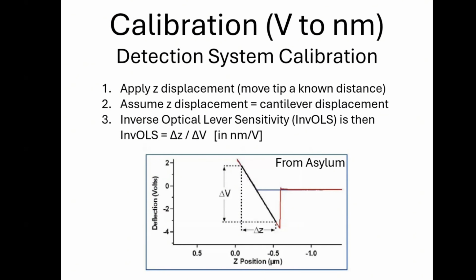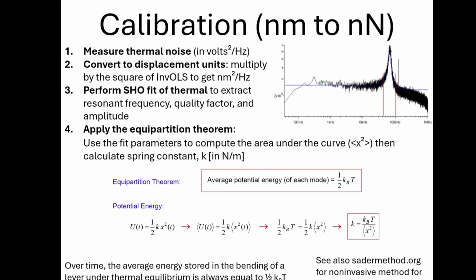First, we need to relate the photodiode voltage, the cantilever deflection in volts, to a cantilever deflection in nanometers. To do this, we do a force curve on a hard surface, where we move the tip a known distance and measure the deflection in volts. This volts to distance comparison gives us what is known as the inverse optical lever sensitivity, or invols, typically in nanometers per volt. Now that we have the deflection in nanometers, we recall that we determined force from Hooke's law, so we need to figure out the spring constant. With K and delta Z, we can then calculate force.